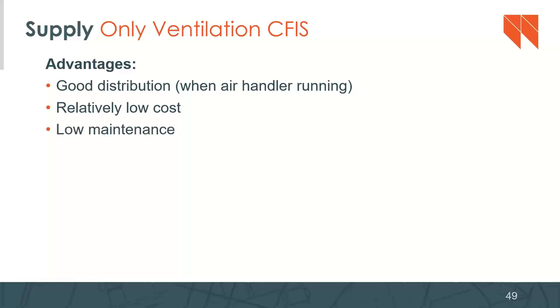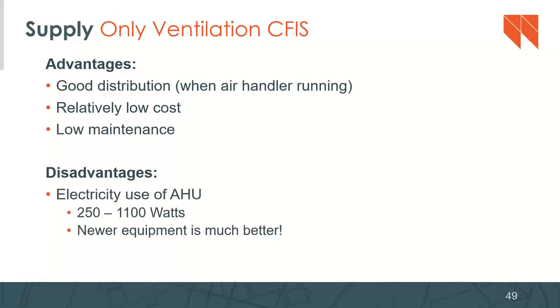So anyway, it's also got relatively low cost. It's got low maintenance. Some of the disadvantages are that the electricity use of an air handler can be quite high. Newer equipment is better, but if you were trying to use the traditional supply only, working this into your air handler, the air handler would usually have to run to get it distributed. And so there are systems out there where you can tell the air handler to run intermittently throughout the day in order to provide the ventilation to the space that 62.2 requires.